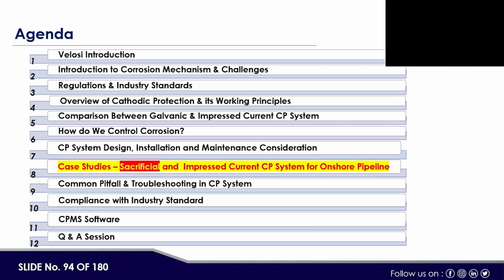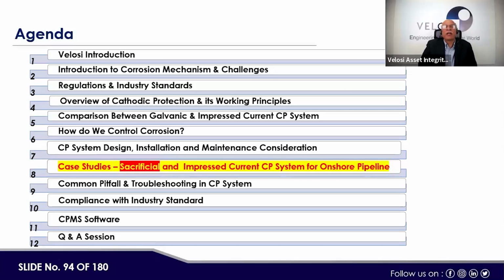Got it. Next question: how does the surface area of exposed metal affect CP — will the anode be sacrificed more quickly? Yes. Normally, when pipelines are protected by a CP system, it's understood that the pipeline is protected by a coating system, and the coating failure rate would not be more than about 1% per year, or maybe less. If there is more failure of the coating system, the current requirement will increase, and the sacrificial anode would be consumed more quickly — that's the normal consequence. Mr. Abdullah, would you like to answer this as well, if you can see the screen?